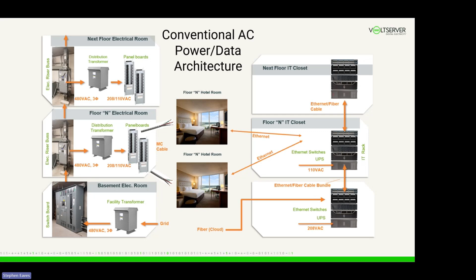Very quickly, this is a conventional AC power infrastructure. From the left side, you come in with a service entrance feed to a switchboard, and in a big building, that goes up to vertical electrical risers that then break out 480 volt power into distribution transformers that break it down to 208, 110 volt feeds. That is then brought into here, what we're showing as hotel rooms. There's also a parallel data infrastructure coming up with Ethernet or fiber connections to the IT stuff in that building, and that's kind of the way things are done now.